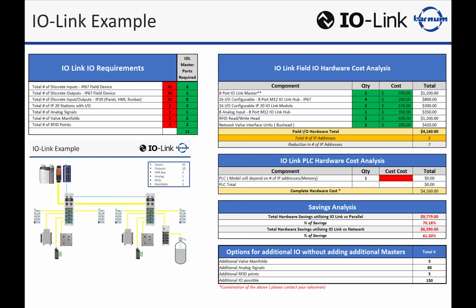Pretty simple. Right on. Hey, one question we got from a couple of our viewers is, is there any length restriction to run IO-Link? And I'm assuming that's the question from your IO-Link master to, say, a hub or to an IO-Link device. Yeah, because your master, your upper level network, is still going to need to conform to the recommendations from that manufacturer, Ethernet IP not exceeding 100 meters, let's say. So yeah, when it comes down to your block and hub, John, I know there's different distances based on if it's an IO-Link hub or an RFID point. So mainly the rule is you have 20 meters of distance.